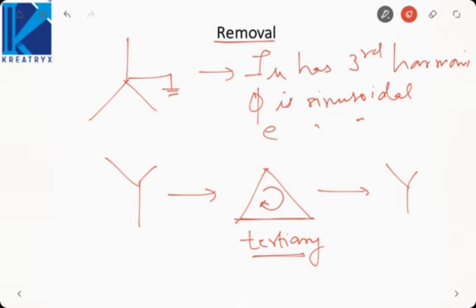So by introducing a third winding, it is called a three winding transformer. The third winding is called the tertiary, which is present between the primary and the secondary stage. Okay. So this way also we can make the EMF sinusoidal. The tertiary winding will take the third harmonic magnetizing current, so EMF will be sinusoidal. Okay, this is how we can remove it. Another purpose of the tertiary winding can be, if we connect capacitors across it, then we can do power factor improvement.